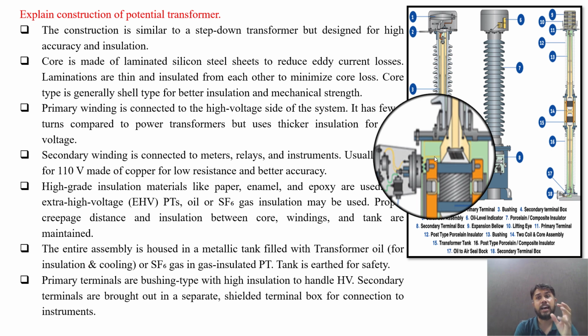Primary terminals are of bushing types with high insulation to handle high voltages, and secondary terminals are brought out in a separate or shielded terminal box for connection with the instruments as well as to the control panel for the indication purposes and to the relaying circuits.